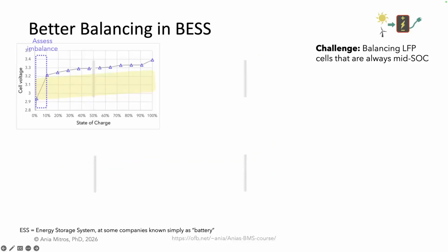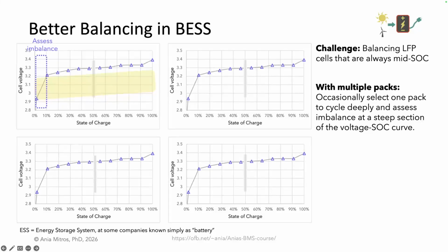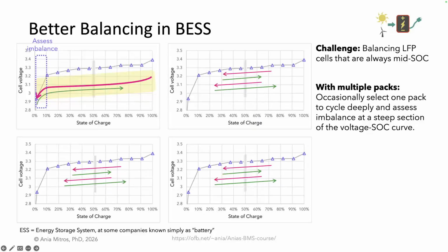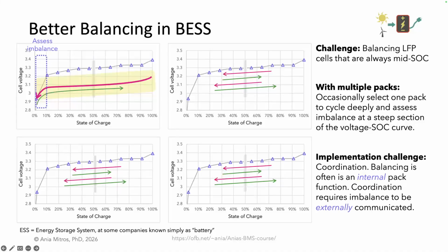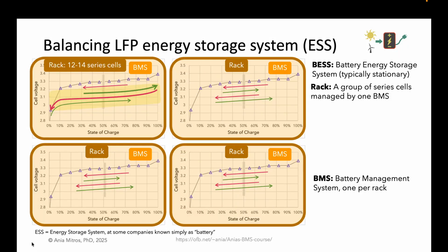Here's what I'd recommend. Oftentimes, grid energy storage involves multiple battery packs. Select one of the multiple packs for deeper cycling. Discharge that one pack to nearly empty and balance it, while the rest of the BESS continues to operate as usual. Then, return the one pack to normal operation. The trick is coordination. Balancing is usually thought of as something that a pack does internally and implemented thus. The idea on this slide requires a central controller to coordinate the packs and requires each pack to communicate some estimate of its imbalance externally to indicate that it might need balancing and also that it is done balancing. A typical architecture for a stationary battery energy storage system groups perhaps 12 to 14 cells in series into a rack with an associated BMS.